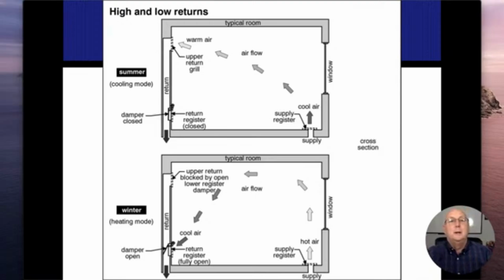In other words, they're showing the top drawing being in cooling mode, so in the summer. The air conditioning is running. If I want to add cool air to the room, that means I want to remove hot air from the room. The hot air is always going to be higher, so I want to remove air from the top. So the bottom register, I'm going to close that register, close that damper. That way air won't flow in through there, and it's going to pull all the air from the top where it's warm, and we're going to pull that down to get reconditioned.